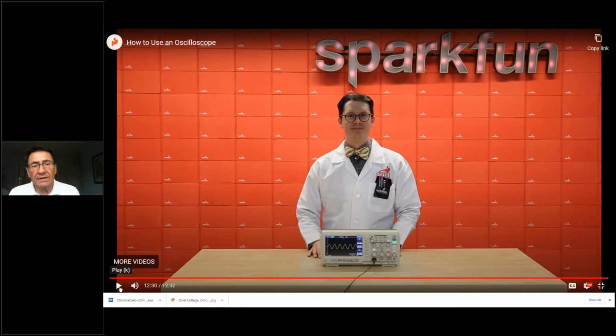For using an oscilloscope on a VFD, a 100 megahertz scope with a 10 times probe is really all you're going to need. You'll be able to read all the signals just fine, and the scope will have enough resolution and bandwidth to deal with anything we throw at it in the VFD troubleshooting arena.